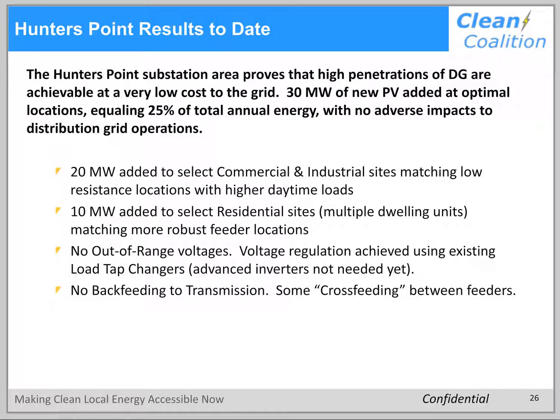We got 10 megawatts on select multiple dwelling unit sites, apartment buildings essentially, which typically are also on more robust feeder locations. We had no out-of-range voltages, so we achieved voltage regulation with the existing load tap changers, without even bringing advanced inverters into the model. And we had no backfeeding to transmission, though we had some cross-feeding between feeders, as mentioned earlier.